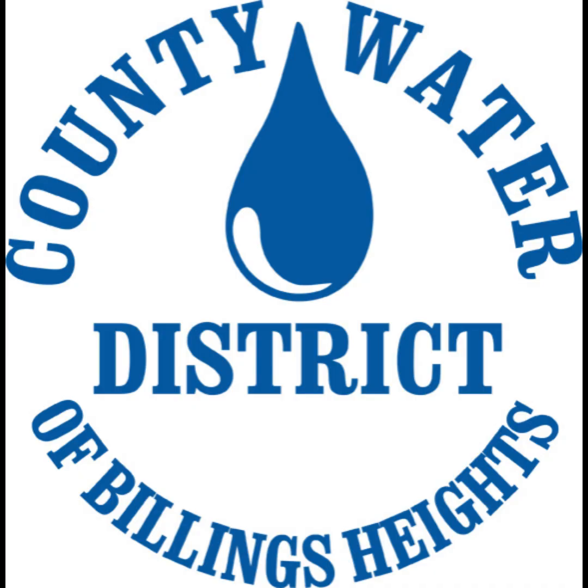Now I'll discuss the alternatives. The first alternative was increasing the smaller diameter mains near Lake Almo. Handout number 2 displays the alternatives. There are 2 sub-alternatives. Alternative 1A, which is displayed in red, includes upsizing about 4,600 linear feet of 8-inch PVC with 12-inch PVC. Alternative 1B, which is displayed in orange, included upsizing about 8,700 linear feet of 6-inch and 8-inch PVC with 12-inch PVC. Here are the water modeling results for the projected year of 2047.